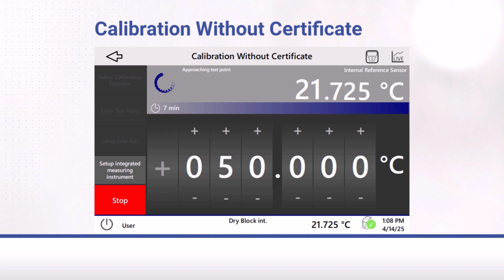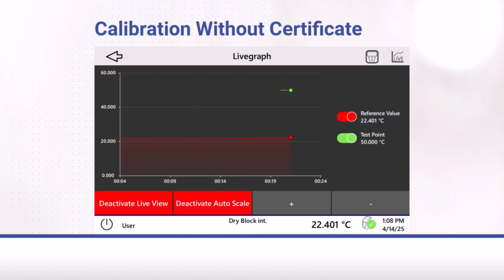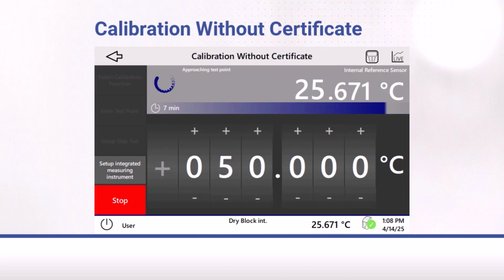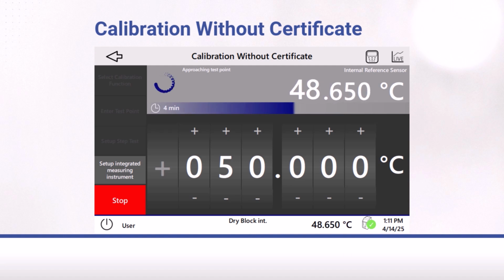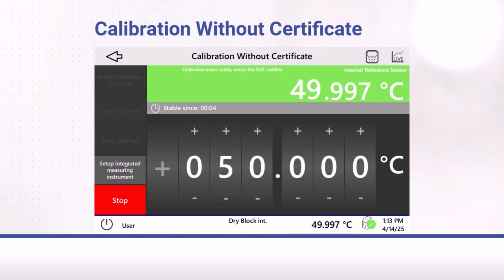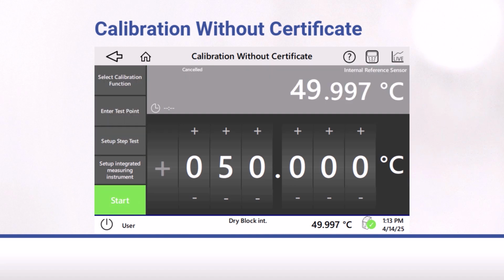The test point is approached and held. Tap the live graph icon to see the real-time temperature reading from the reference sensor. Tap Stop to end the calibration. If your temperature calibrator is equipped with an integrated measuring instrument, you can configure it using the button.